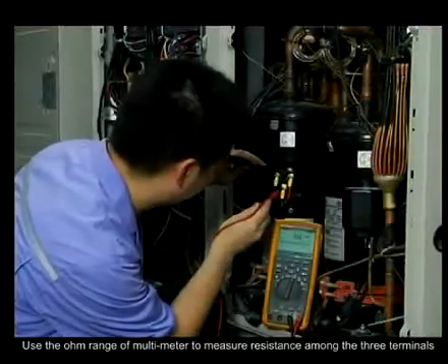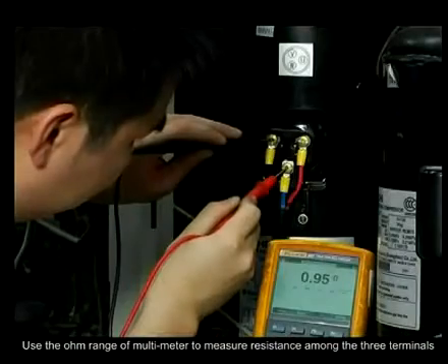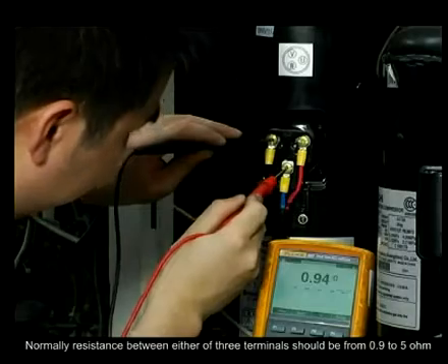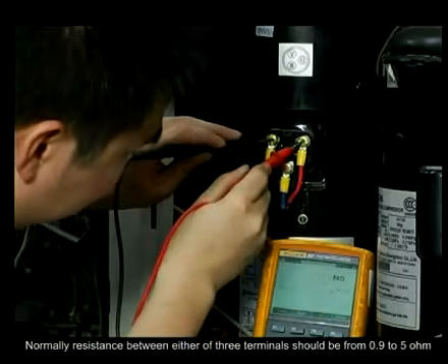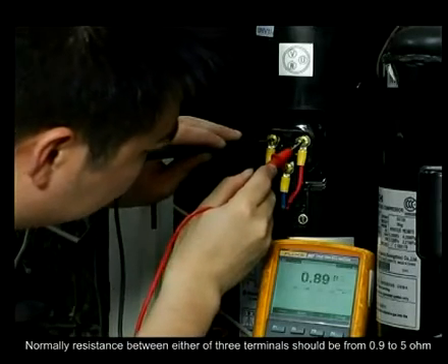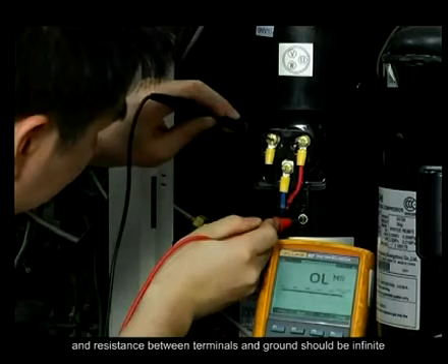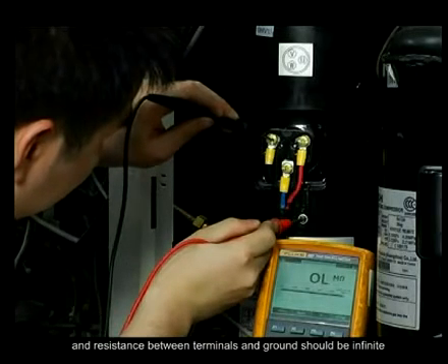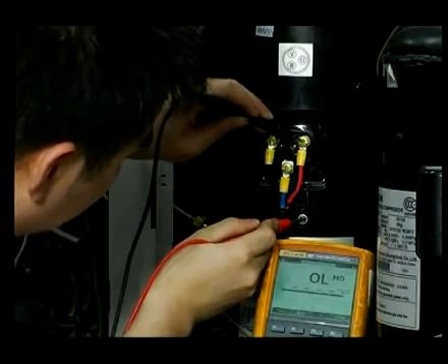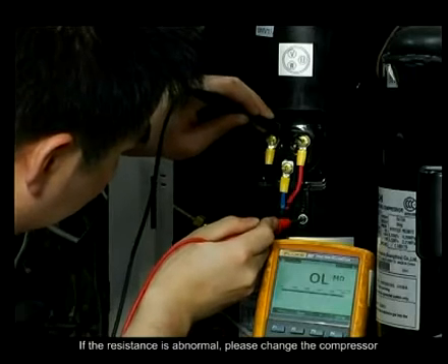Use the OHM range of a multimeter to measure resistance among the three terminals. Normally, resistance between any two of the three terminals should be 0.9 to 5 OHM, and resistance between terminals and ground should be infinite. If the resistance is abnormal, please change the compressor.